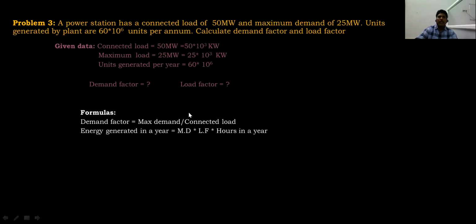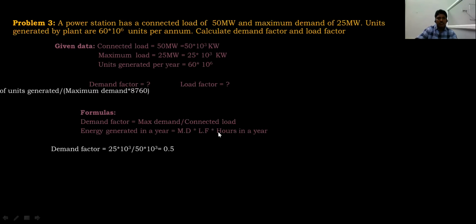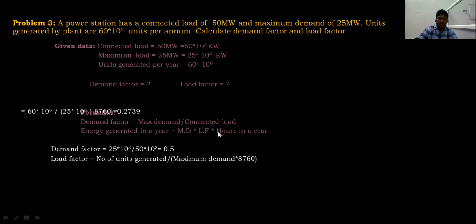That gives you the demand factor. Load factor is equal to number of units generated divided by maximum demand into time. Here the number of units in a year is given, and the maximum demand is given, divided by hours in a year. This will give you the load factor. The load factor in this case is 0.2739 and the demand factor is 0.5.